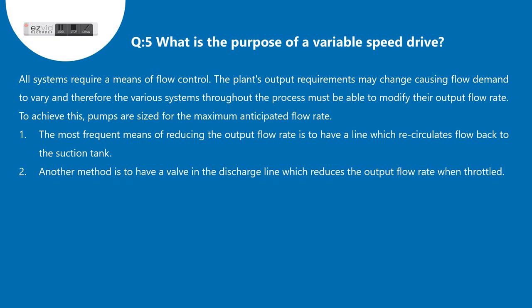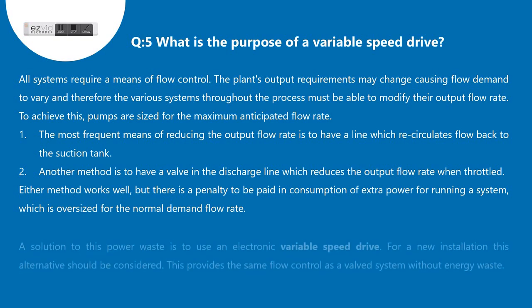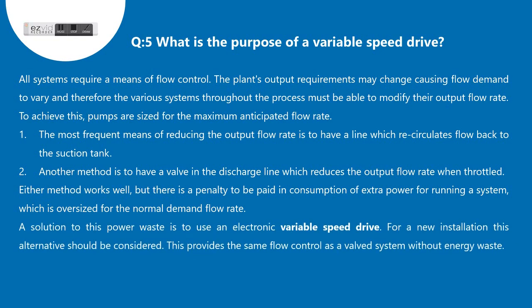Another method is to have a valve in the discharge line which reduces the output flow rate when throttled. Either method works well, but there is a penalty to be paid in consumption of extra power for running a system which is oversized for the normal demand flow rate. A solution to this power waste is to use an electronic variable speed drive. For a new installation this alternative should be considered.